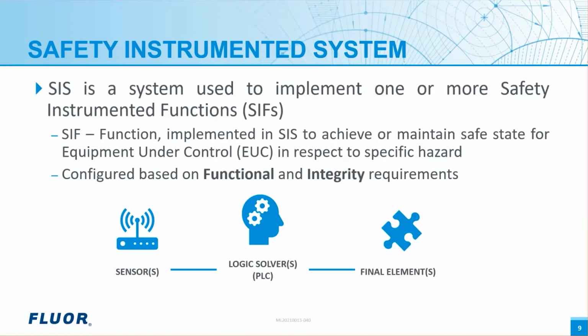An example of functional requirements is in a tank: a SIF is typically provided for protection against high level to avoid an overfill scenario. The tank level is measured, and if the level crosses the set limit, the inlet valve is closed. So to prevent overfill, the SIF has approximately 5 minutes to act, which is the process safety time.